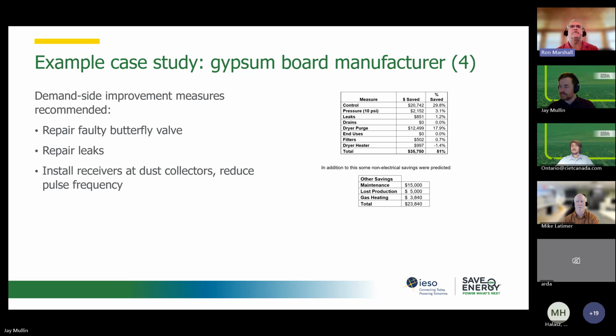Yeah, so for the improvement measures, we have a table showing them, and we can see that the new variable speed drive compressor is quite significant, and the air dryer purge savings were significant, and very often that's missed, right? If an auditor is just looking at the supply side, just the compressors itself, and ignoring the dryer. So we also recommended, obviously, to fix that butterfly valve, fix leaks, and install some receivers at the dust collectors to reduce the pulse frequency and give the cleaning method a lot more power to clean the filters.